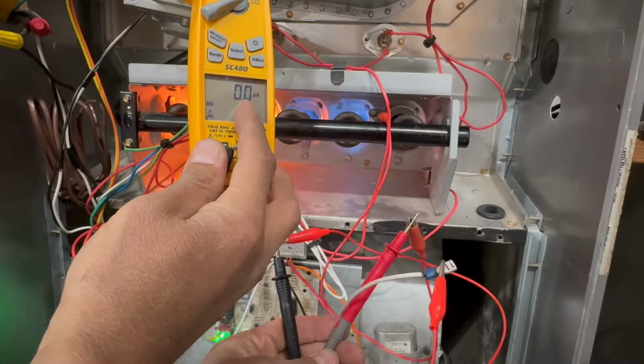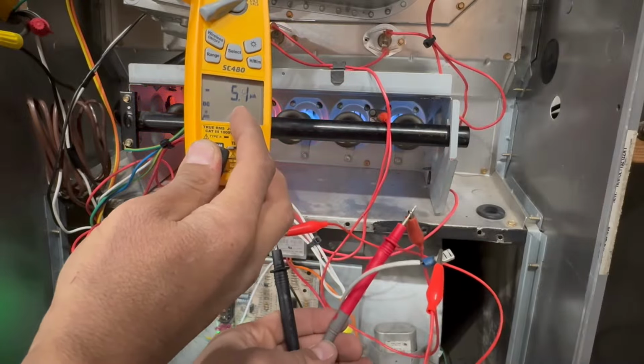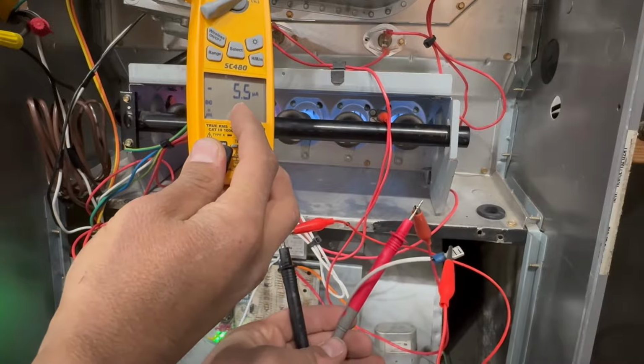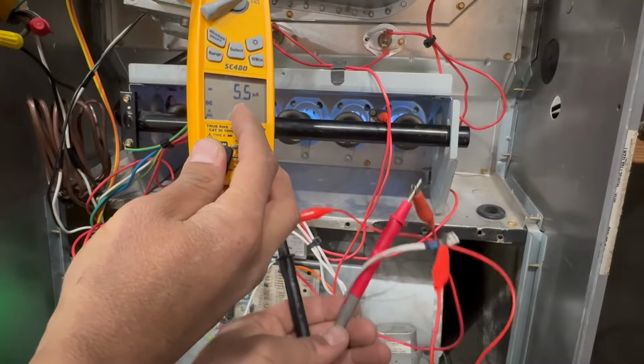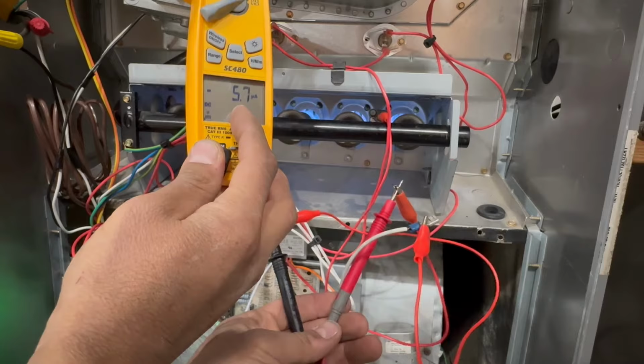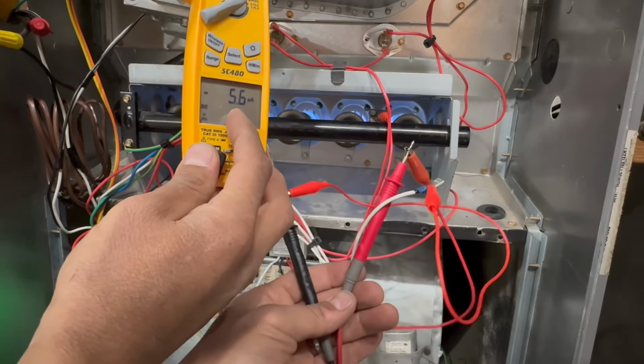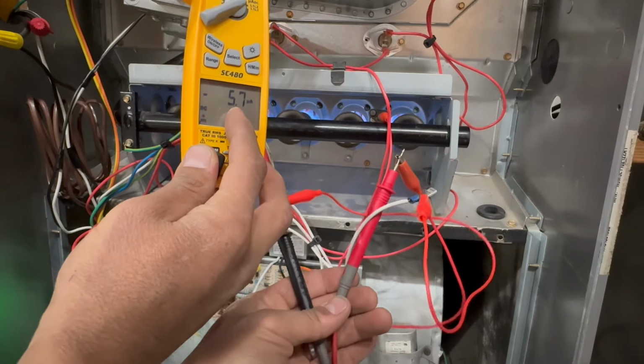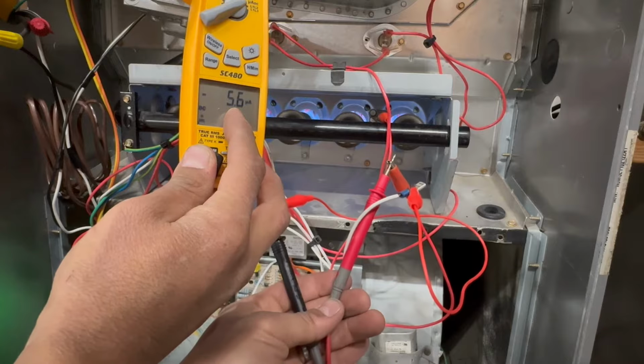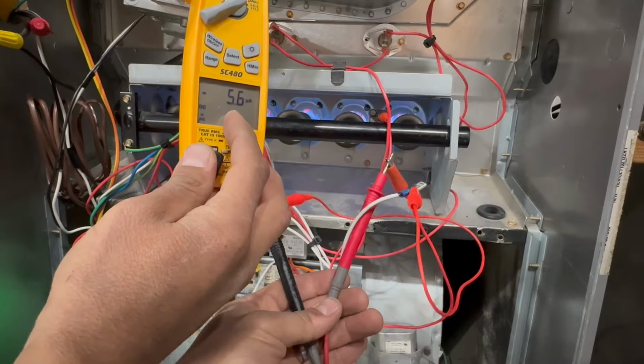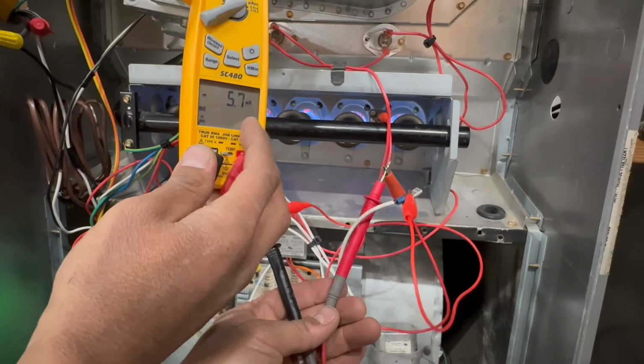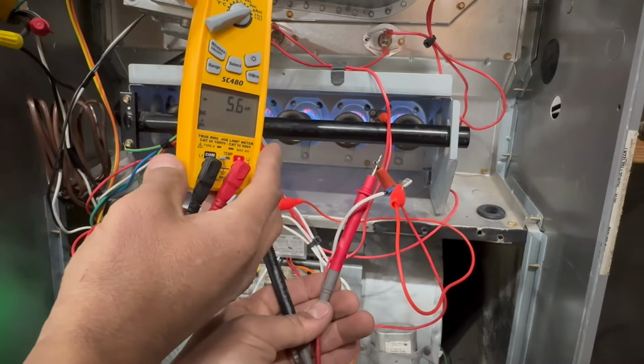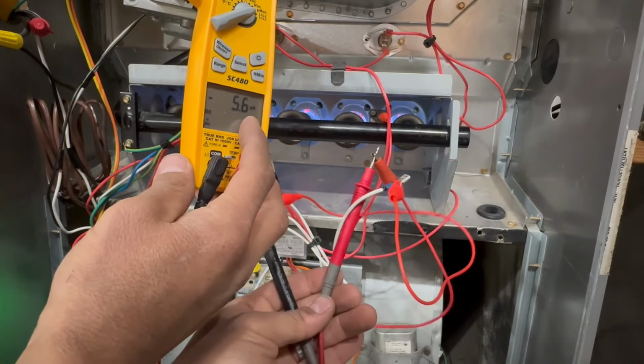Once we get flames. Right there. We got 5.5. We're getting microamps. And to be able to check this properly, you have to have the leads and the alligators connected, because right now that direct current is literally going through your meter. So if you disconnect right now one of those wires, it's going to turn off because it's part of the circuit.